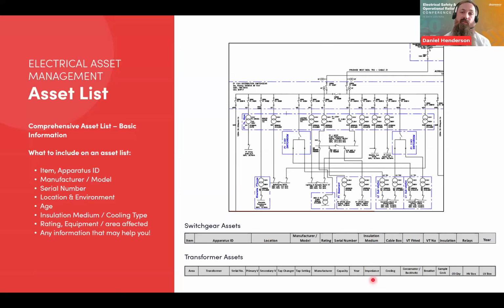Again, manufacturer, the capacity in kVA, year of manufacture, impedance, again, is important, especially when we're matching. It links into the fault levels, but also if we're paralleling transformers, we need those to be similarly matched from that perspective.